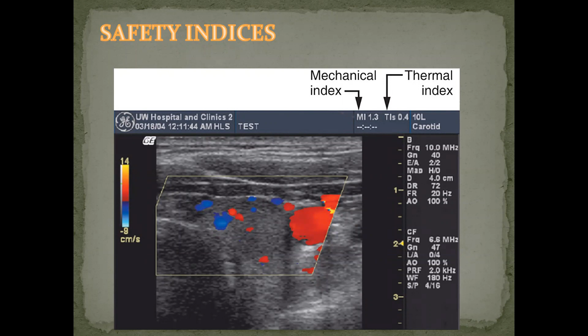But the other thing too here is looking at this on the B mode, they are scanning at 100% power, and also on the color flow, scanning at 100% power. That is not necessary. You do not need to scan at 100%. You can drop it quite easily and still produce excellent, perfectly good images.